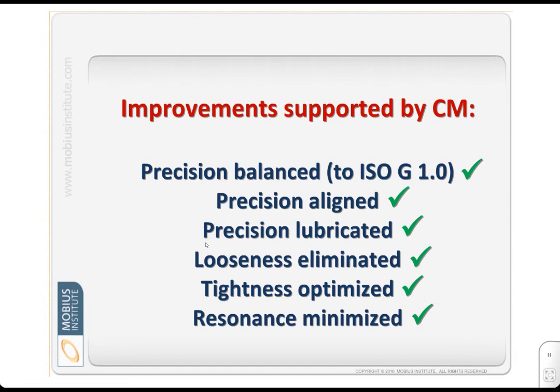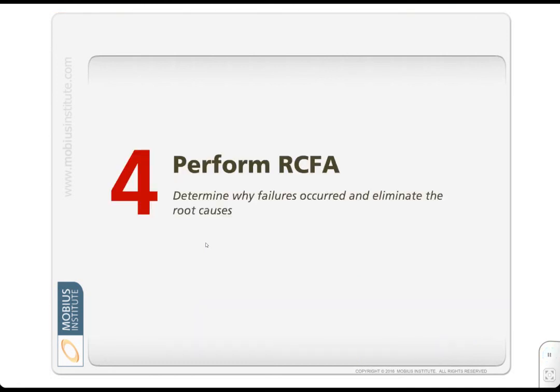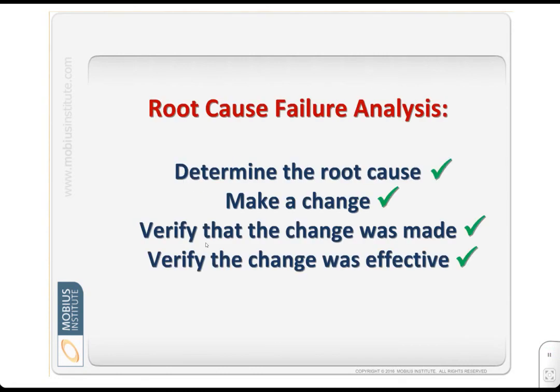We need to eliminate resonance. It just amplifies vibration. We need to look at all of our installation practices, and even if the condition monitoring group aren't involved in the installation itself, we can be there immediately afterwards to do a sort of QA check. Hey, how did it go? Are there any problems before we start operating the equipment for the longer term? And we can get involved in root cause failure analysis. So we can determine the root cause of the equipment failure, and then a change needs to be made. We need to verify that the change was actually made and that it was effective.